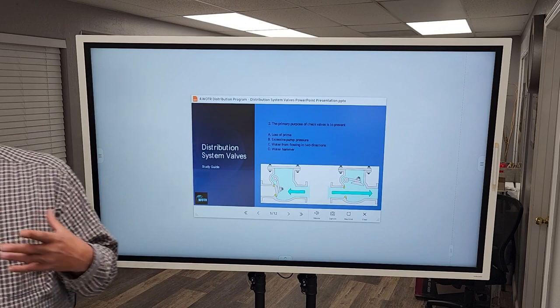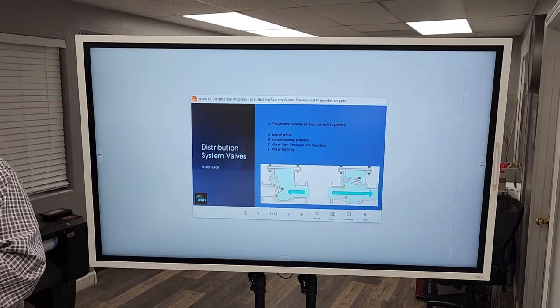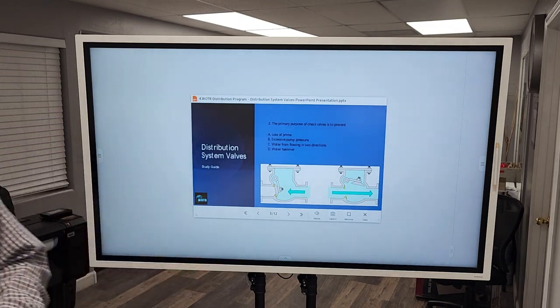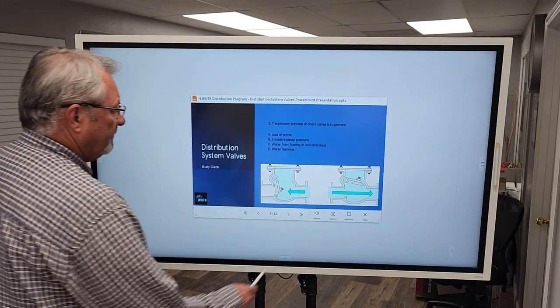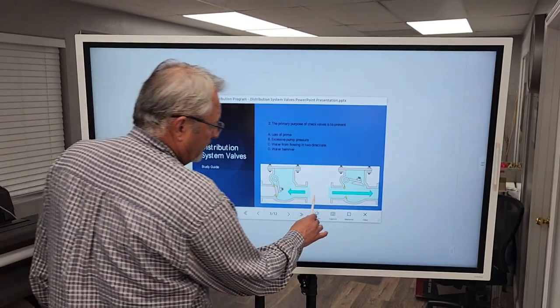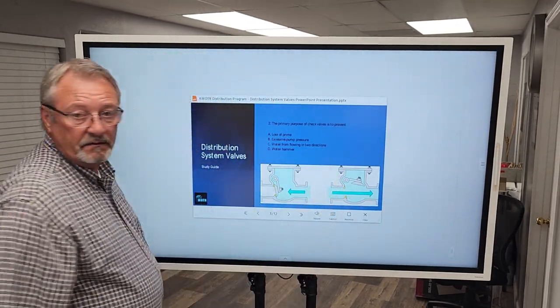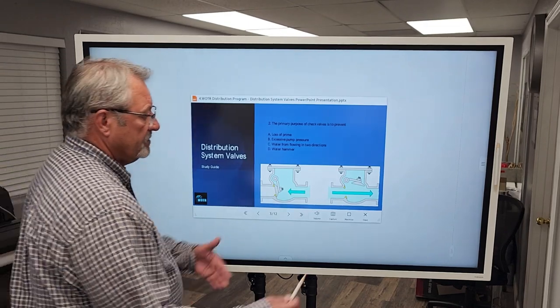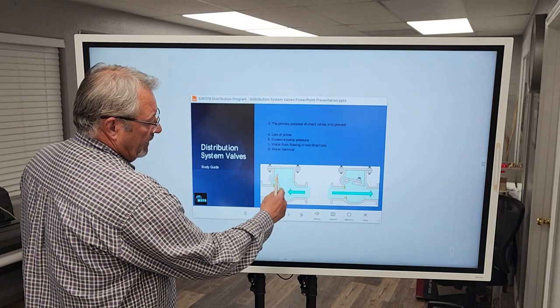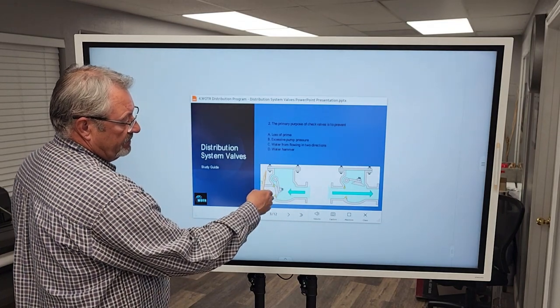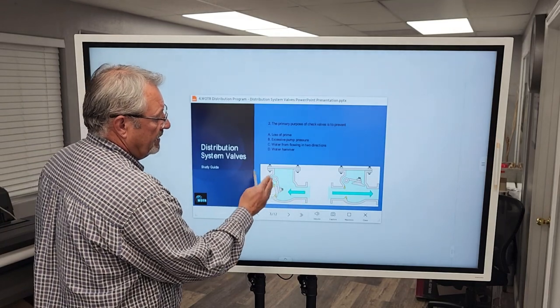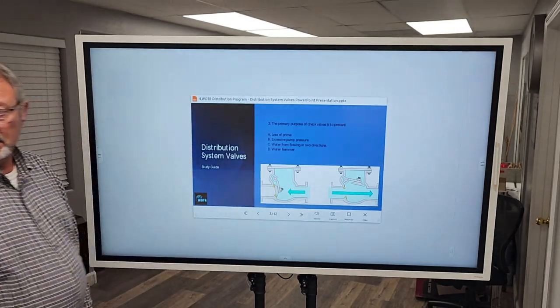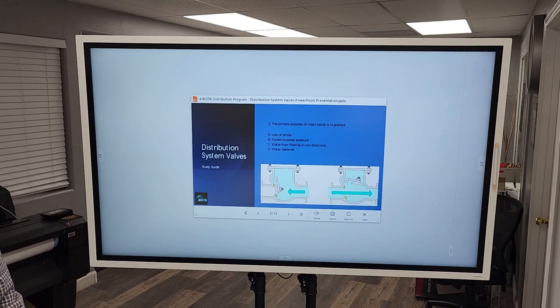One of those methods that we do this is with a check valve. A check valve allows water to only flow in one direction. As the water flows through the check valve, the way that we want it to move, the valve stays open. If there's a reversal in flow, if the water pulls back, it slams that check shut. It slams it shut and it won't allow water to flow backwards. And that's one of those methods we use to protect the potable water supply.